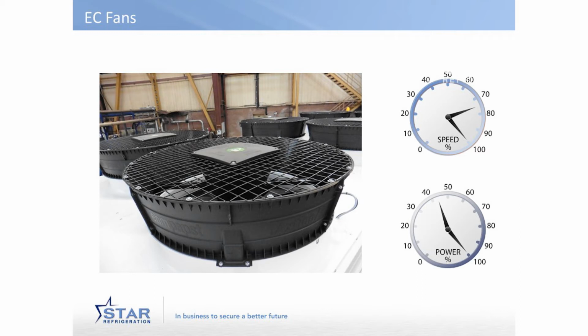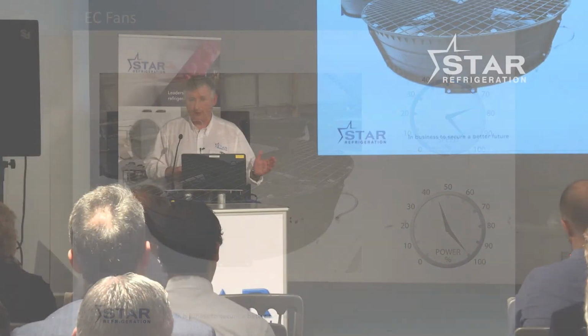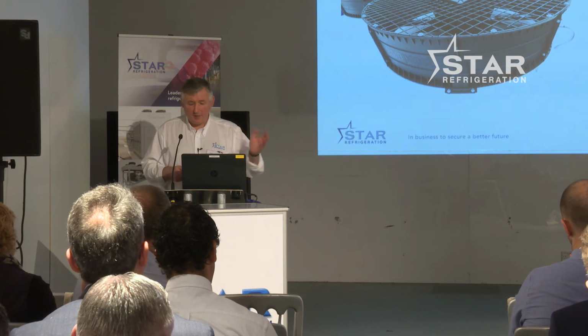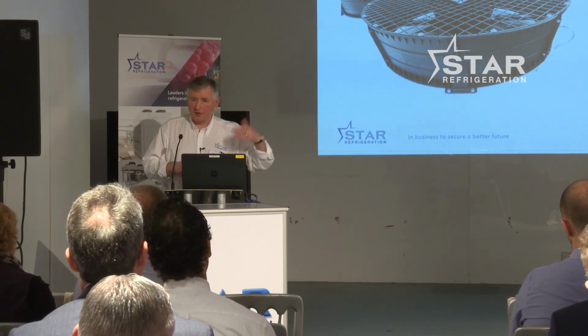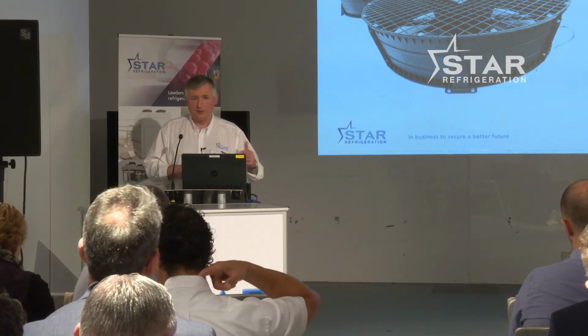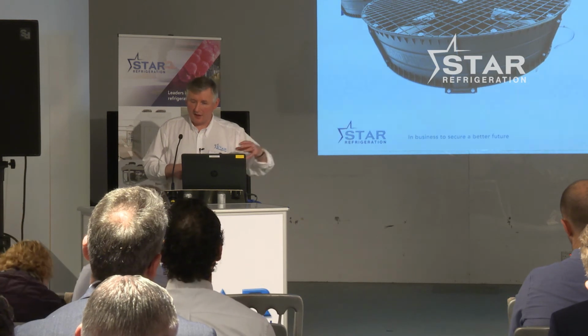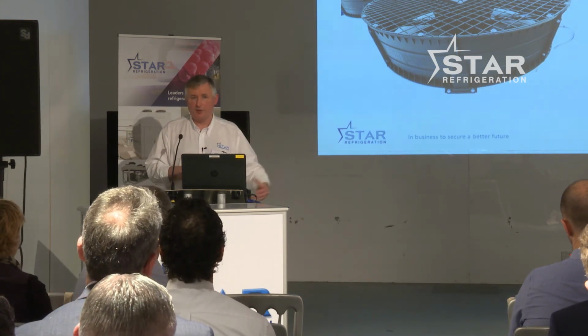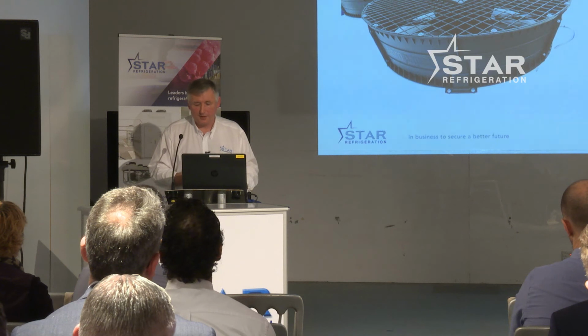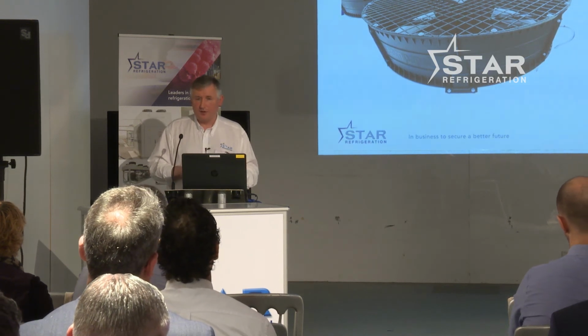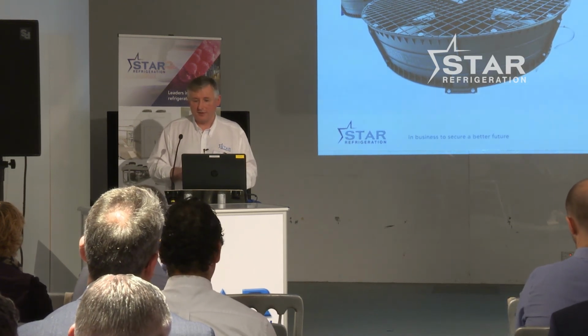The problem with pumps is that as you drop the speed, you reduce the capability to overcome pressure drop. So you need to be careful. If you drop the speed too far in a pump, then it'll be deadheaded and there'll be zero flow. The same kind of applies to fans, but there's generally much less of a resistance to flow. If there's an air duct on the downside, you need to be a bit more careful with variable speed on the fans. But there's huge opportunity for saving energy by reducing speed on fans.